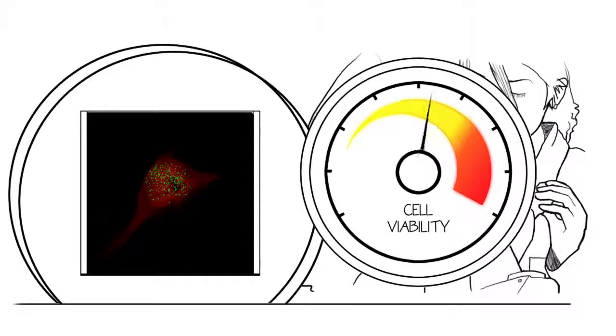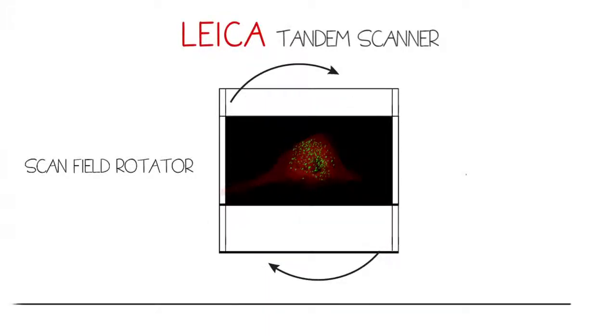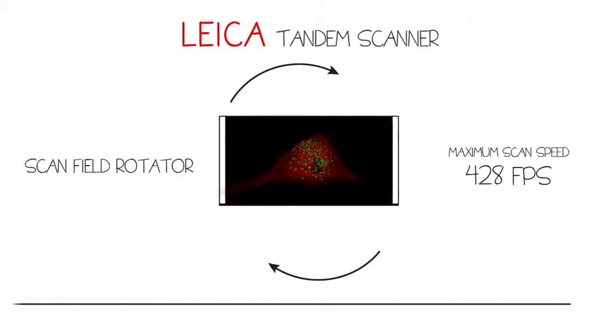The Resonance Scanner provides the benefit of having a short dwell time, which reduces laser exposure and prolongs cell viability. To generate images even faster than 40 frames per second, a scan field rotator can orient the region of interest to increase speed.